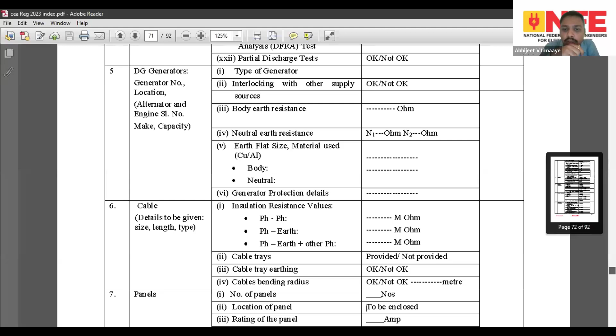When we talk about IP protection of panels, this is a part which is very important for electrical safety. There are a lot of installations, specifically where I work in textile and steel, where you will have fine dust going into the air which can deposit inside the panel, creating a fire hazard risk. So a lot of times conventional panels in the market go with IP4X protection, but you need to have IP protection in line with the installation. You might have to go for a panel which is IP54, which is dust proof, or even protections like IP65, making it liquid proof, to comply with the installation standards.